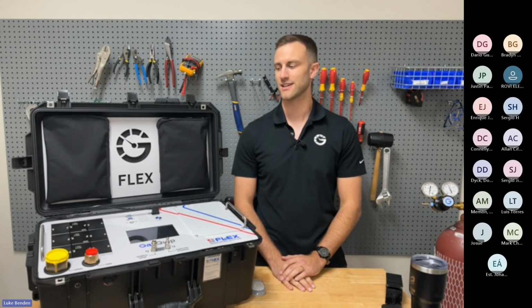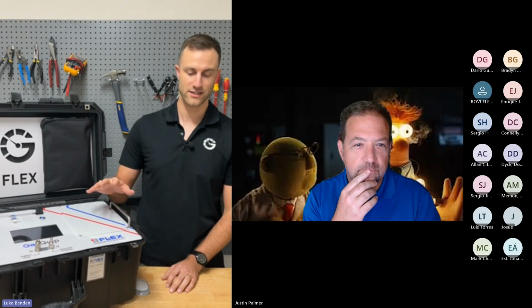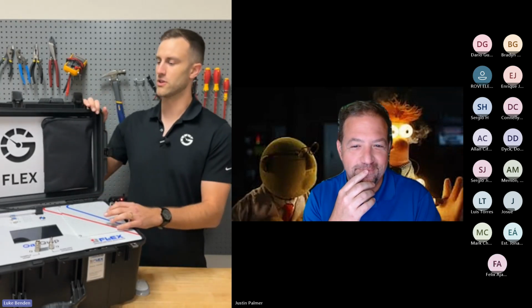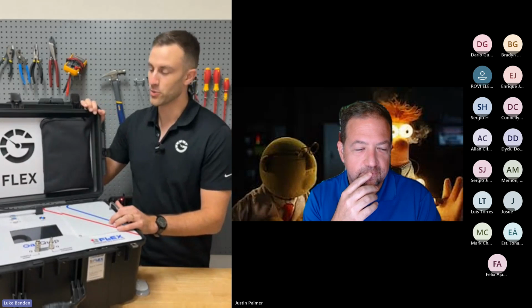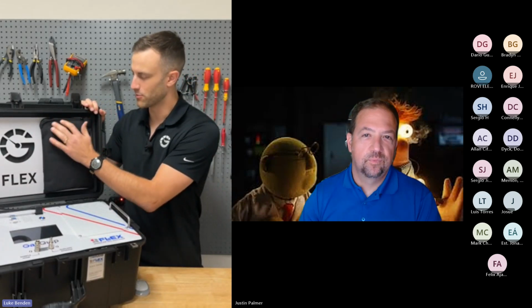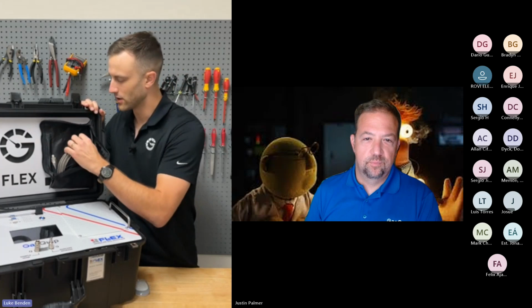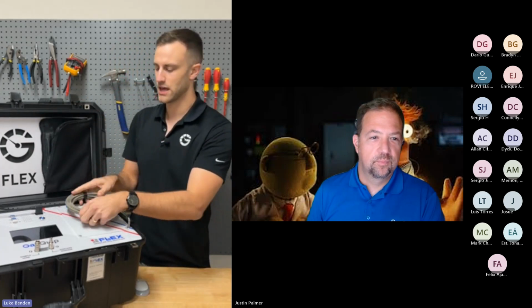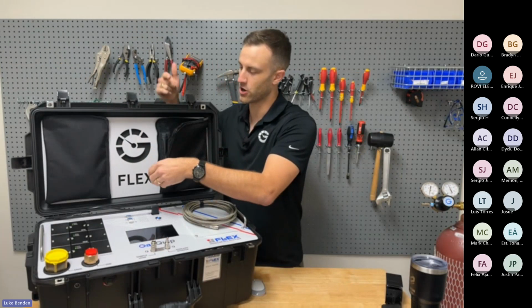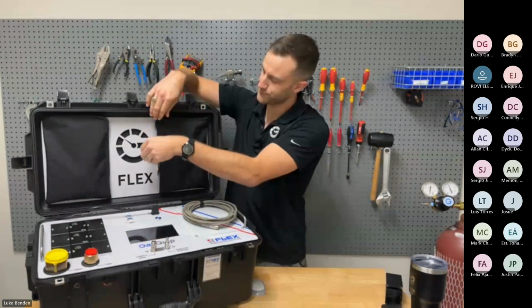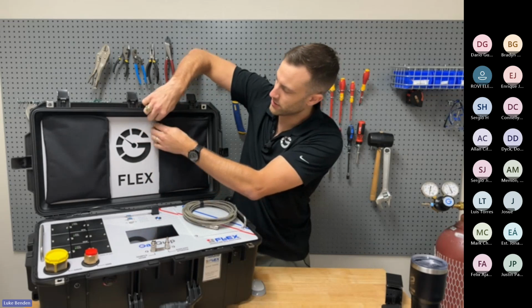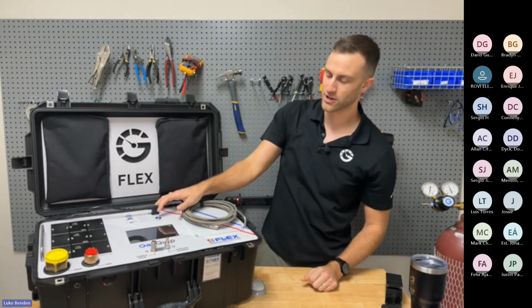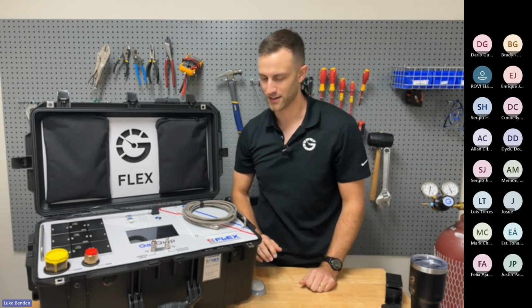Today we're going to show you some of the features and benefits of the Flex and talk about best practices while testing gas. So first off, let's talk about the setup. Whether you have our Flex analyzer or a different analyzer, most of them are built into a Pelican case like this. Open this up, and inside this compartment will be a sample hose, the gas sample hose, and also a power cord. We've already got our device plugged in, so we'll just leave that in there. Once you have that plugged in, either to 120 or 240, you'll turn the device on, press this power button on the top, and get it powered on.